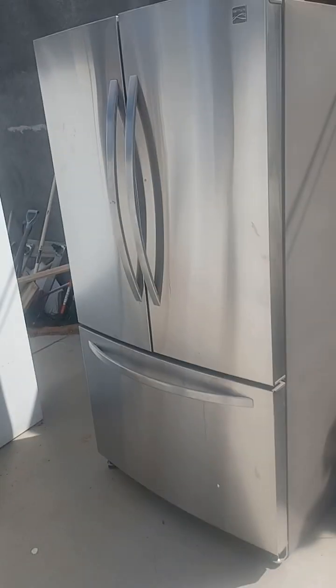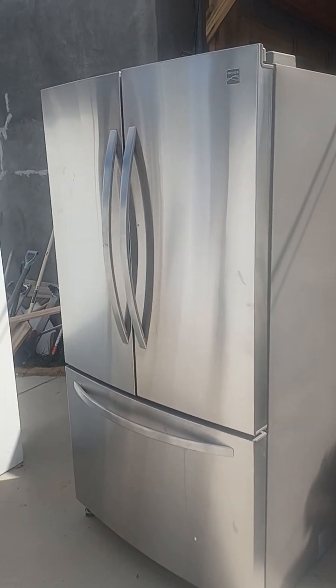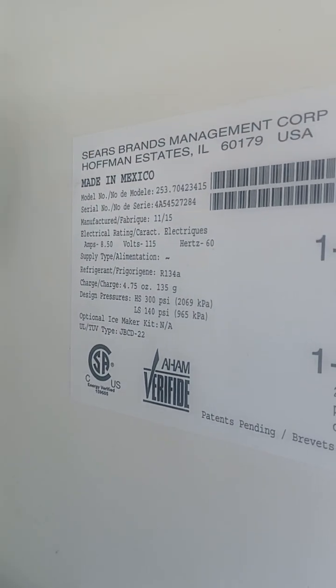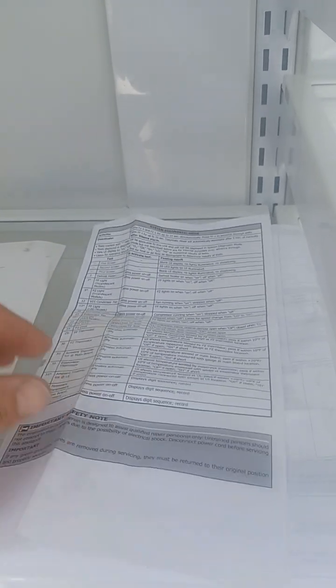Hi, I'm Kerry. This is a 22 cubic foot refrigerator with French doors and a freezer underneath. It's unplugged, and I'm troubleshooting it. It was having a defrost issue, so I wanted to know how to jog this refrigerator into manual defrost mode, and I did find the tech sheet eventually.